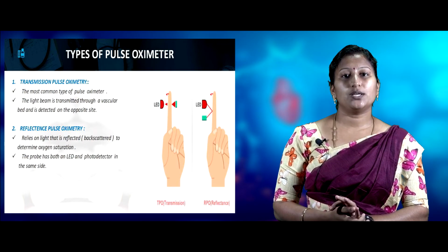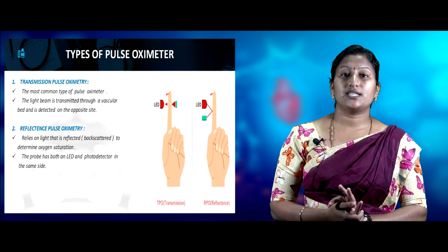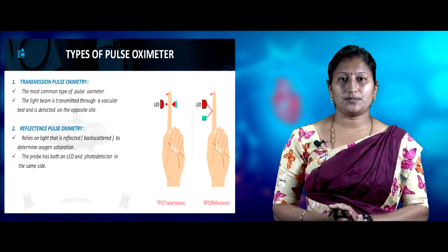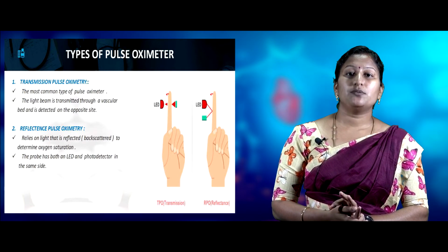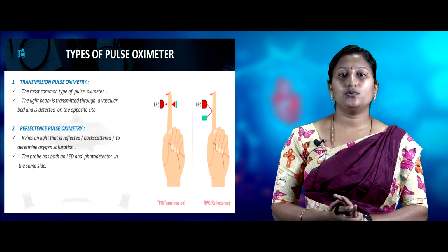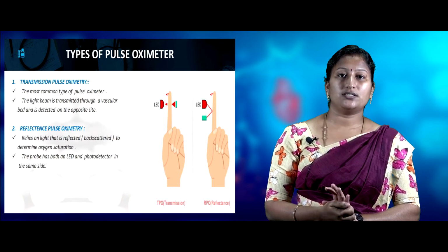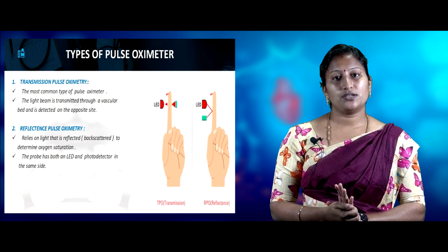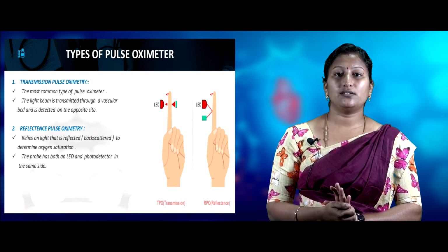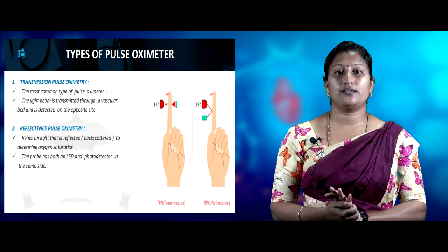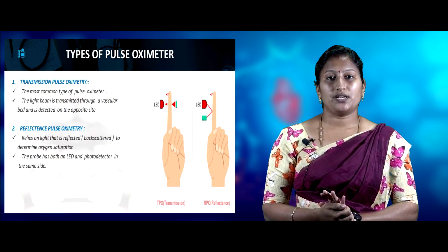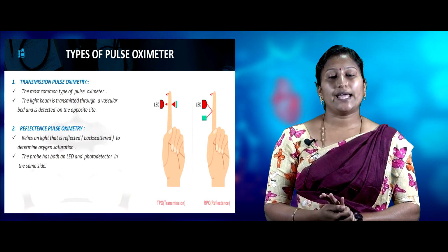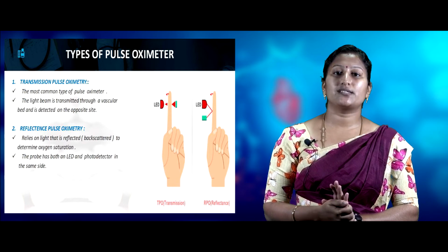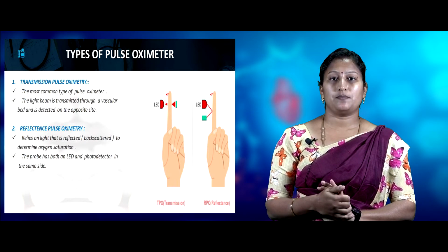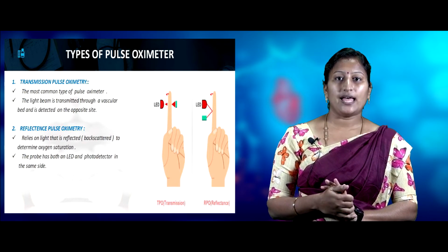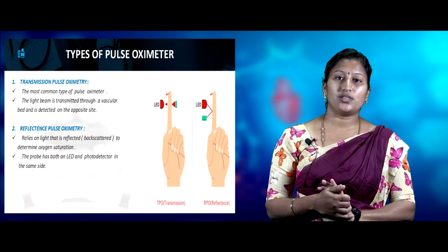There are two types of pulse oximeter: transmission pulse oximeter and reflectance pulse oximeter. The transmission pulse oximeter is the commonly used type. In this, the light beam is transmitted through a vascular bed and detected on the opposite side. Reflectance pulse oximeter relies on the light that is reflected by the vascular bed. In reflectance pulse oximeter, both the LED and the photodetector are placed on the same side.